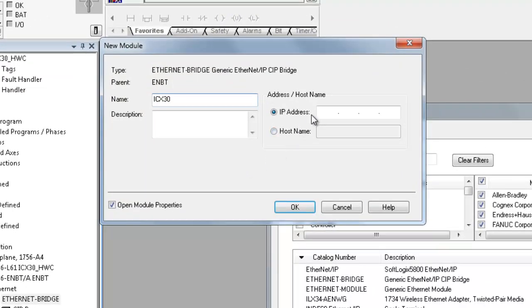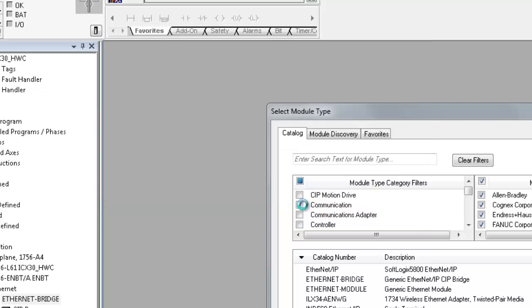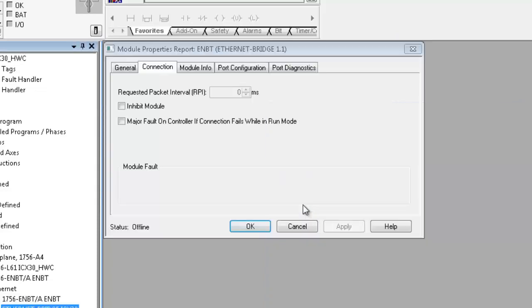This will be the Ethernet address of the cellular modem. In the Module Configuration window, give it a name. We recommend the name ICX30. If you name it anything else, you will have to change some of the message paths in the module. Next, put the IP address of the cellular modem, then click OK.